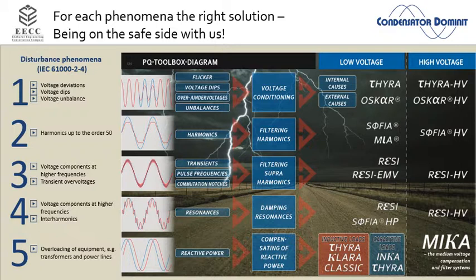I'll ask you more questions, something like, can I have a single line diagram or something like that as well, of course. But the most important question I ask you is, are you causing the voltage distortion by yourself? And do you have any limitations towards the utility, how much harmonic current you're allowed to the grid? If you tell me, yes, my biggest problem is that my utility does not allow me to connect because I'm creating 600 amp fifth harmonic current, then I will normally try to sell you a current control filter, because say 600 amps the utility is complaining about.